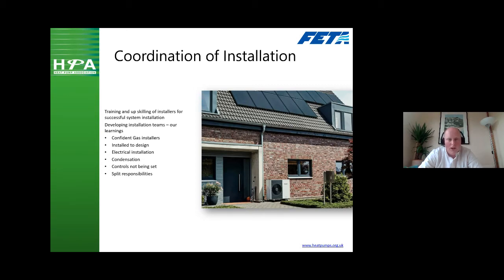It's installing to design. Some of the stories I could tell you about the paperwork saying one thing and the actual install being completely different are quite shocking sometimes. The electrical installation, which I've mentioned, particularly with the controls aspects and making sure that you've got power to the external unit.